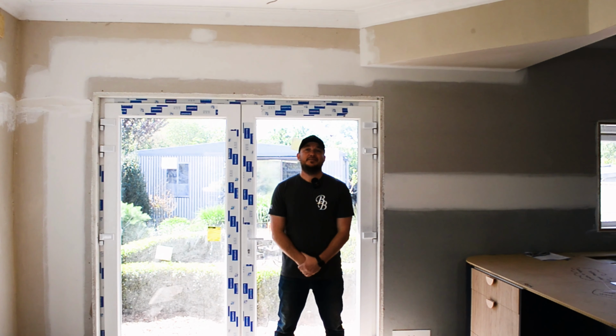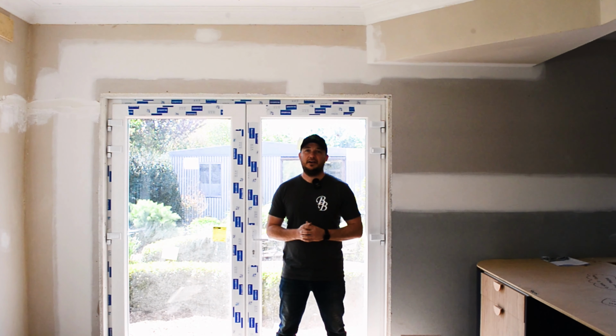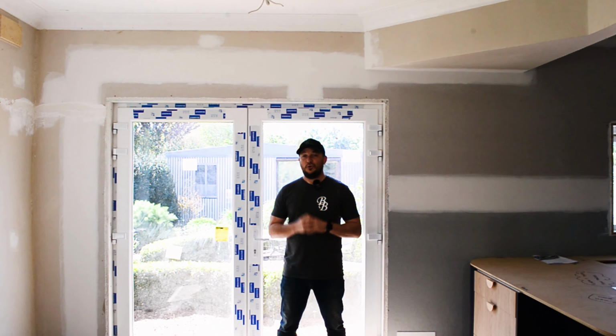Guys, it's been a week since we've been here and done the blower door test with Anthony. As we saw last week, we've gone from over 23 air changes an hour in pre-construction before we started, down to 0.96 air changes an hour, which is in the realms of and a fit for passive house. So this house is not going to be a passive house, but it's got all the elements.